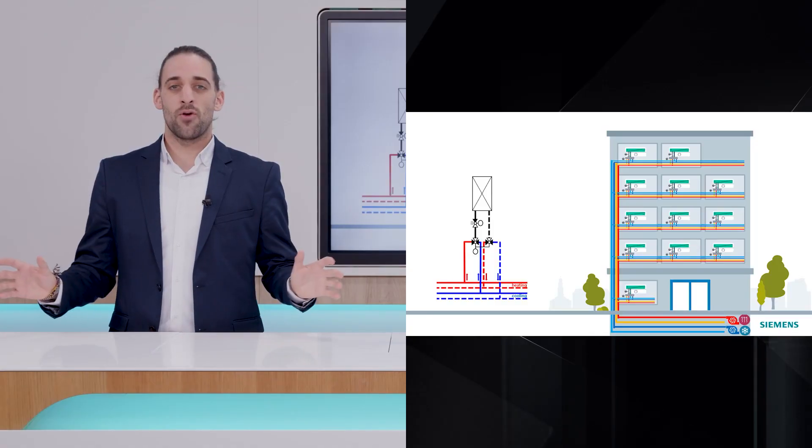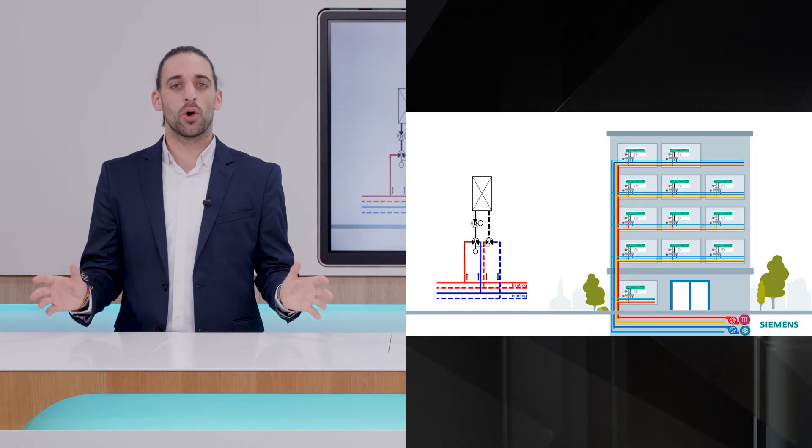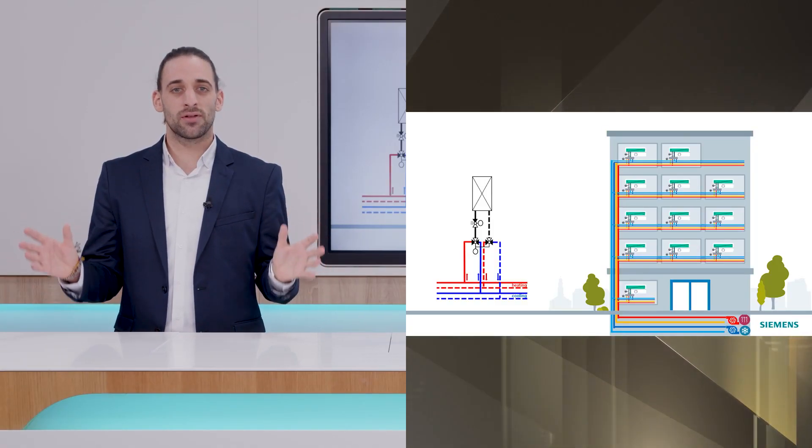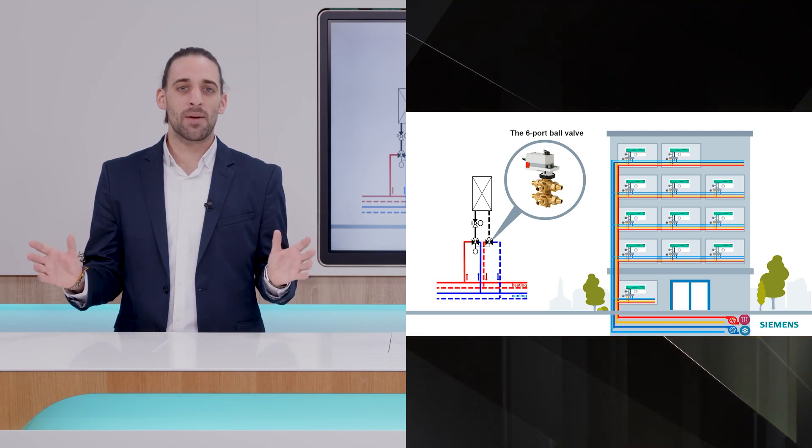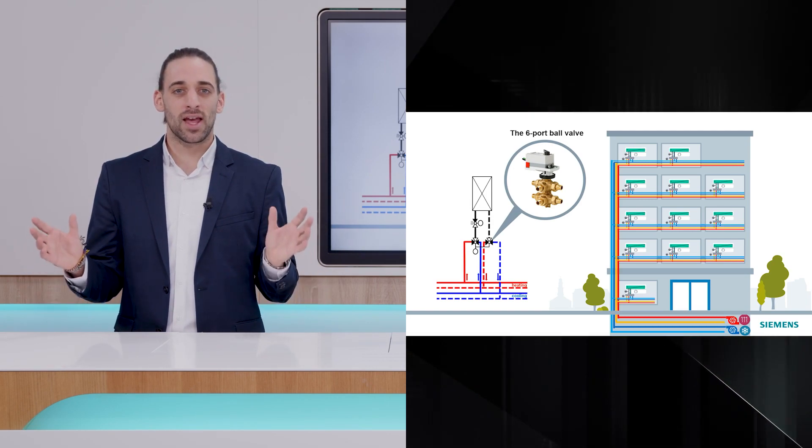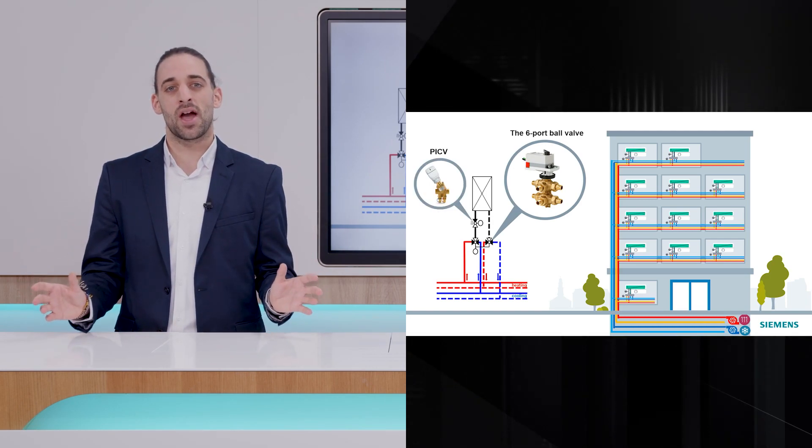For this reason, PICVs started being used in the outlet or inlet pipe of the terminal unit, along with the six-port valve. Now, the switching process is handled by the six-port, while the dynamic balancing is taken care of by the PICV.